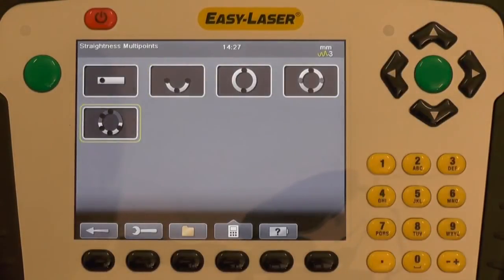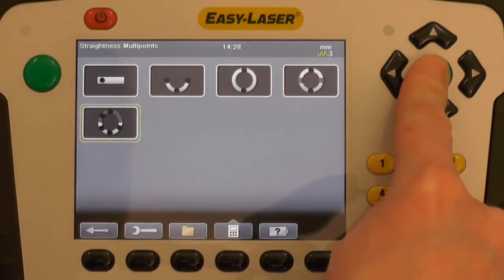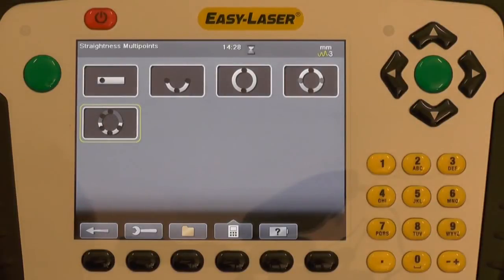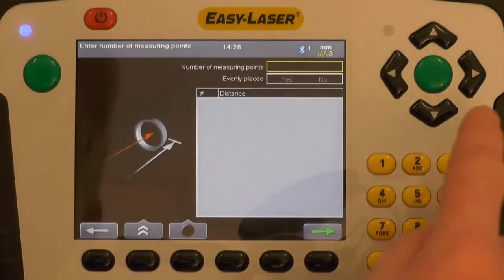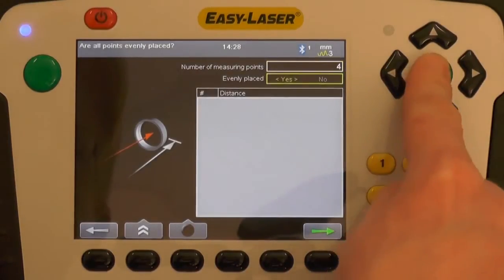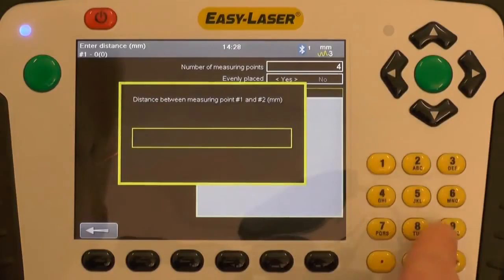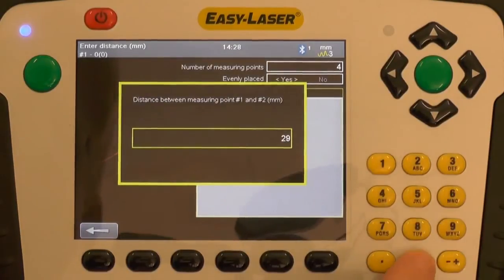Once the laser beam has been aligned I enter the straightness program. In this case I have full access to the bearing journal and will therefore measure multi-point mode. I will set up the measurement dimensions, in this case 4 bearing journals spaced 290 mm apart.